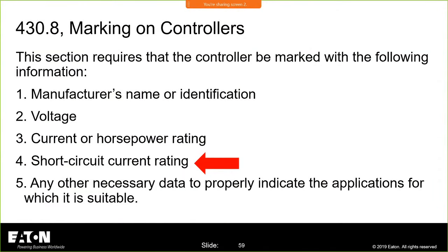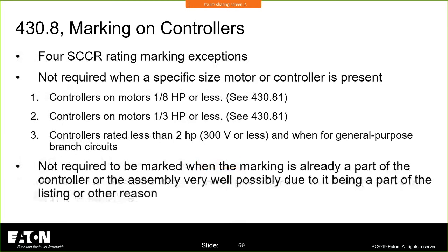So 430.8 has been in there, and it's that line item 4. Again, that was a part of the 2008 version, so we should be very familiar with that, which is automatically done when you buy a listed solution. And then for the SCCR markings, there are some exceptions in 430.8. That's controllers on motors of 1/8 horsepower or less, and then 1/3 horsepower or less. And you have to see 430.81 to get those two requirements or those limitations.